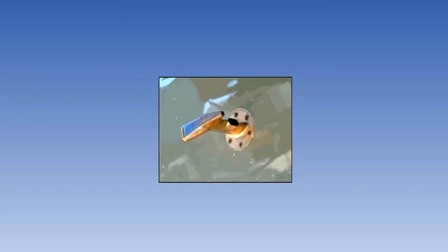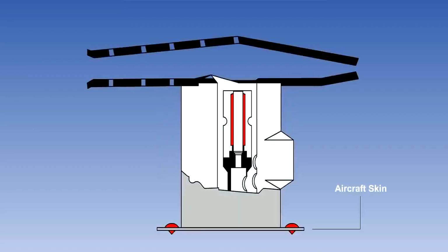The probe is usually constructed from nickel-plated beryllium copper, which provides good thermal conductivity and strength. This type of probe consists of an air intake mounted at right angles to a small hollow strut or casing. Inside the casing is a pure platinum wire resistance sensor.